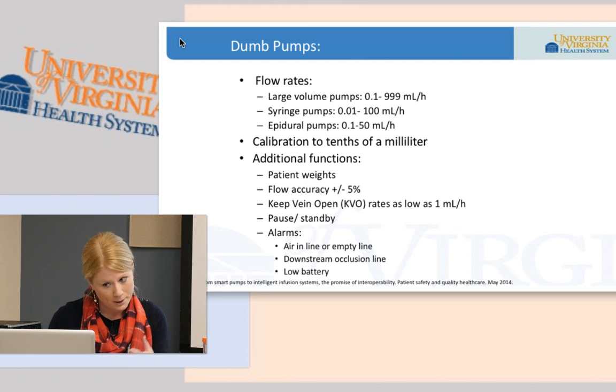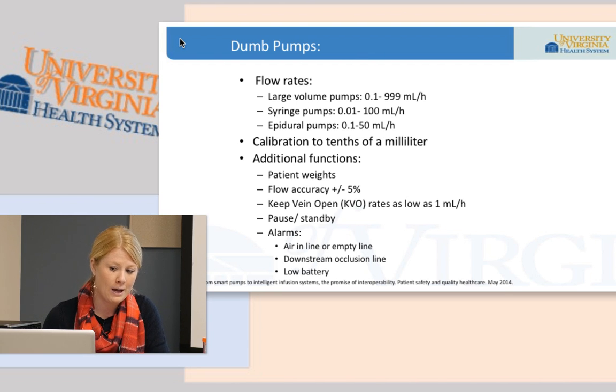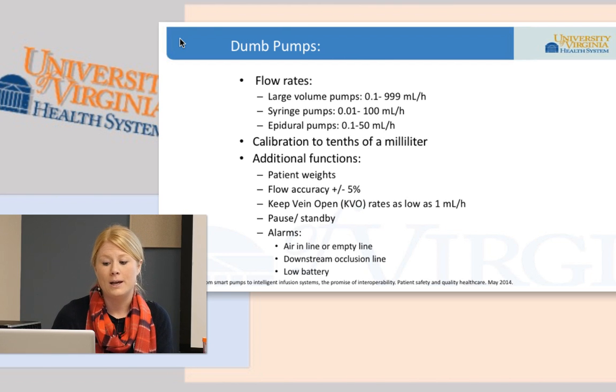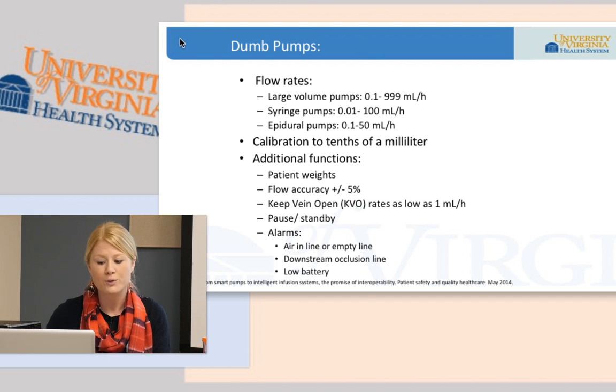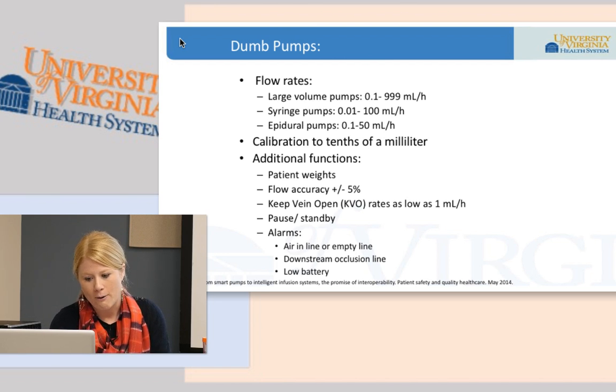Like I mentioned, the dumb pumps, which we now call dumb, but at the time they were innovative and really new to IV medication use, and brought a lot of safety features compared to what we were previously using. They brought the development of flow rate, so the large volume pumps had the ability of running things from 0.1 to 999 milliliters per hour. Syringe pumps had the ability of running things from 0.01 to 100 milliliters per hour, and then the epidural pumps had the ability of running things from 0.1 to 10 to 50 milliliters per hour with calibration of tenths of a milliliter, or for the syringe pumps a little bit further down.